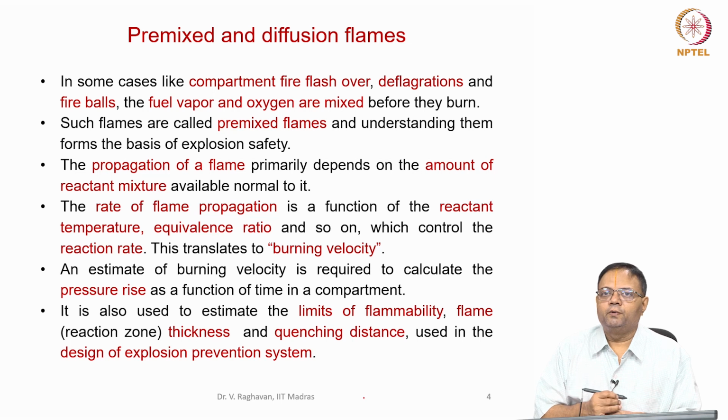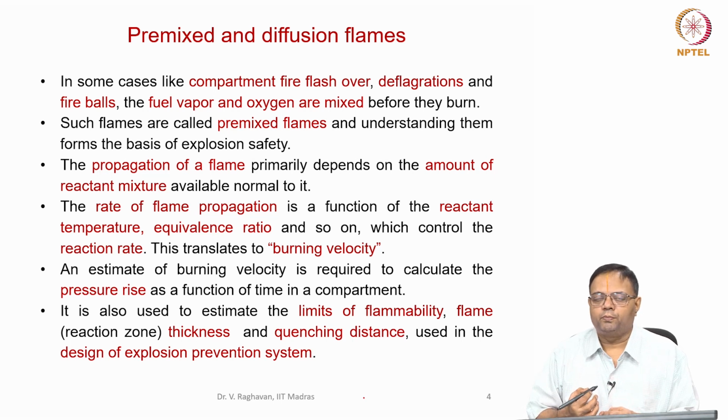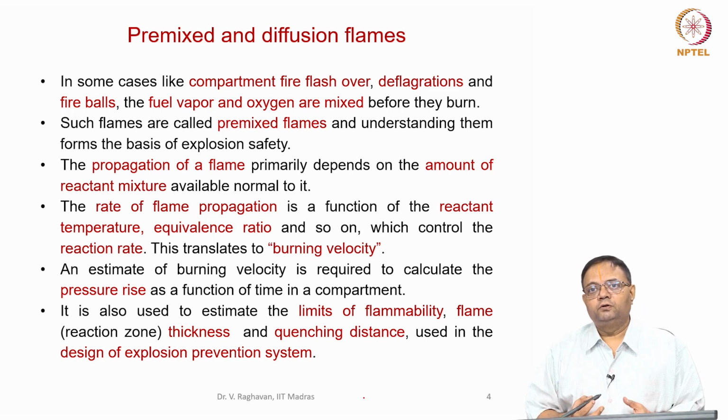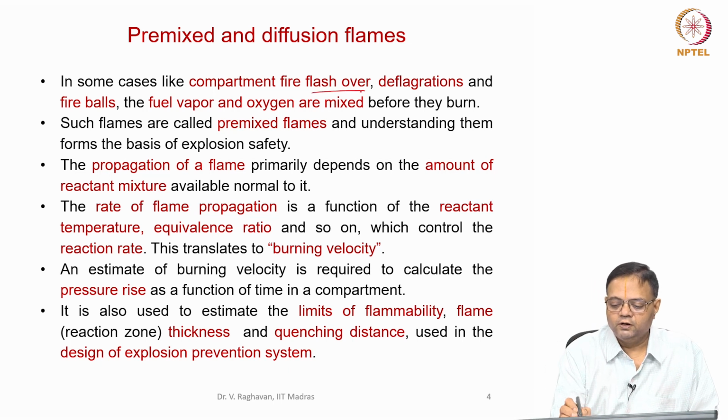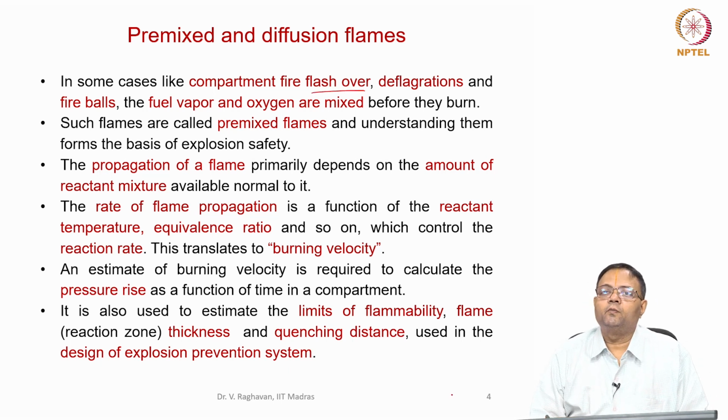So, that is one phenomenon. But if proper ventilation is present, then what happens is the fuel vapors are formed, they mix and form a flammable mixture, and this fire can cause what is called a flashover. That is, the neighboring commodities also will be ignited due to the heat release from this fire.